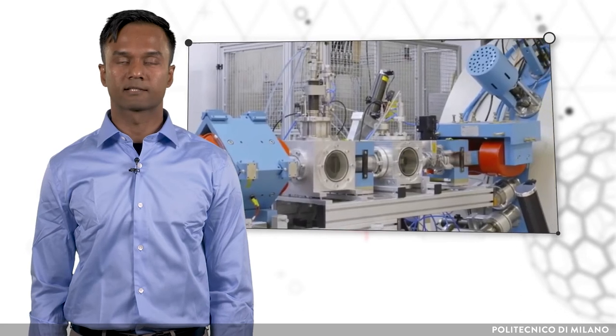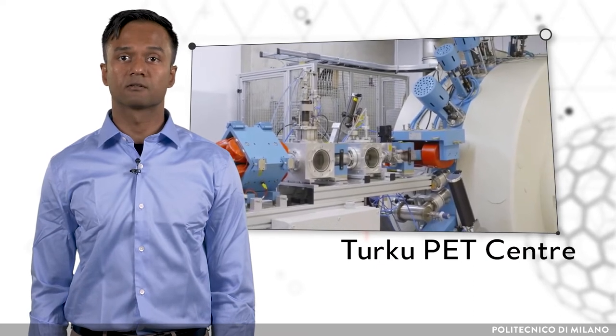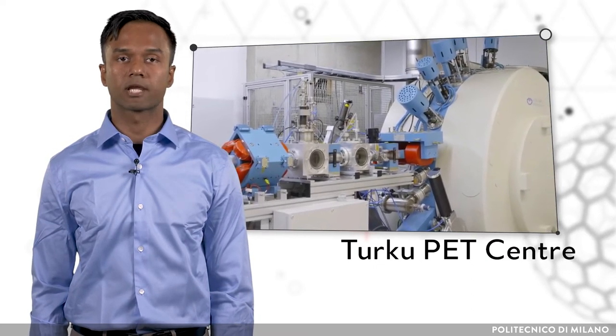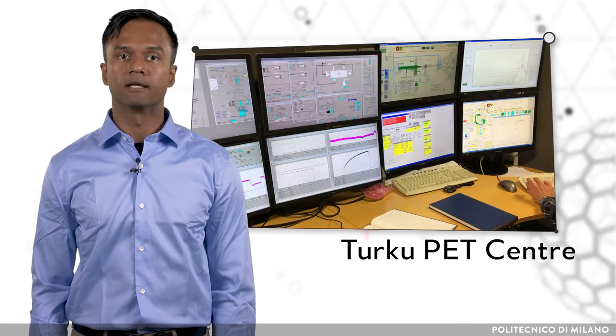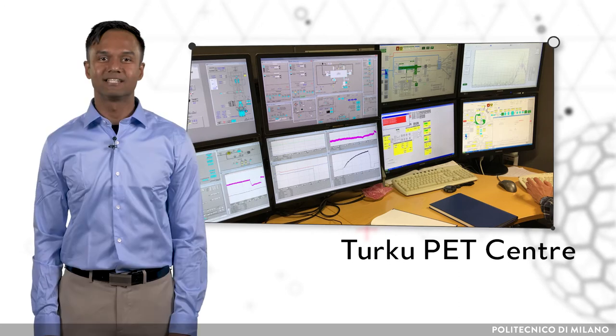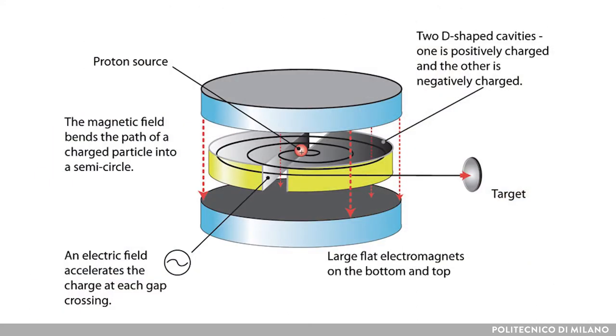Another type of particle accelerator used for production purposes is the cyclotron. Cyclotrons are circular in shape, as opposed to the linear shape of the LINAC. The particle moves in a circular motion under the influence of an electromagnetic field perpendicular to its plane of motion. The D-shaped hollow cavities have oscillating charges which allow for the acceleration of the particle within; due to this acceleration, the particle moves in a larger circular radius with each rotation. As the particle is ejected out, it is guided to hit its target where the nuclear reaction occurs.